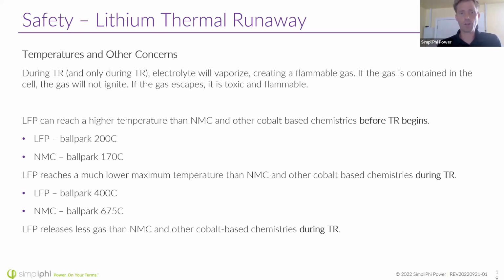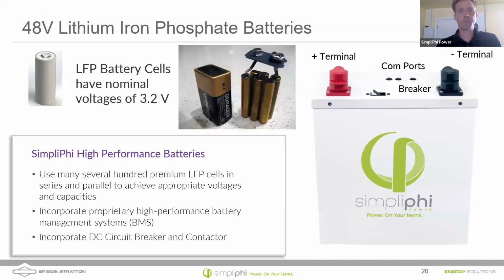So if you force it to go into thermal runaway, you're looking at a maximum output temperature of about 400 Celsius. And with NMC, that maximum temperature is considerably higher. So that's one more reason to avoid that cobalt-based battery cell for home installations.